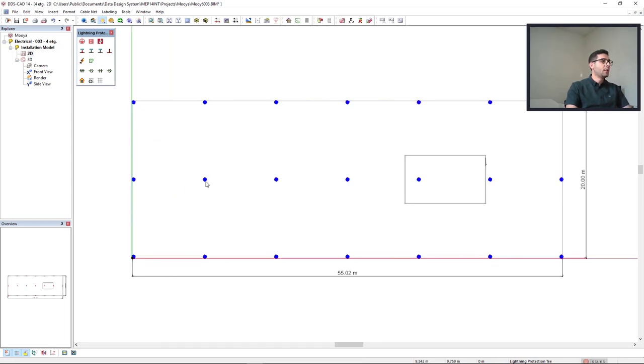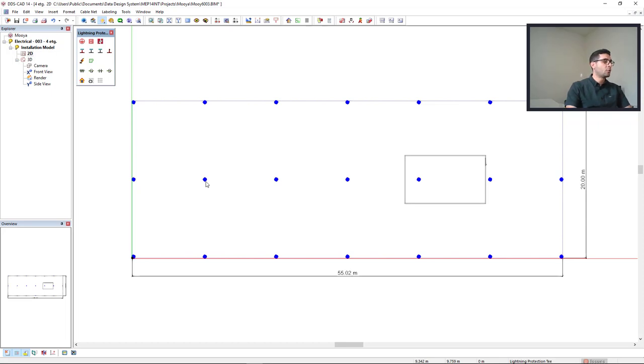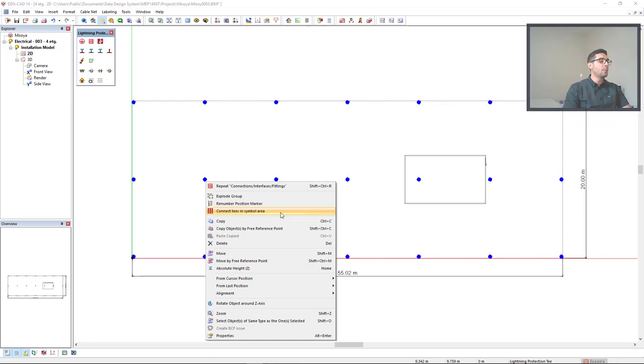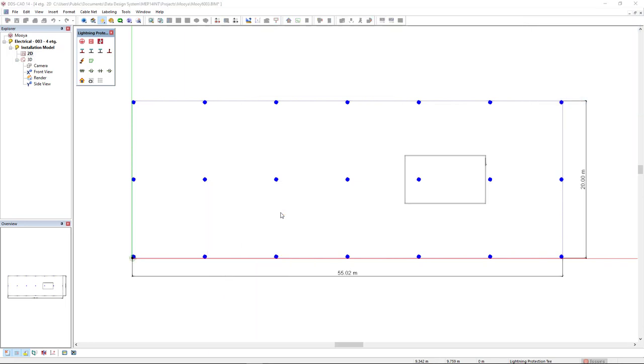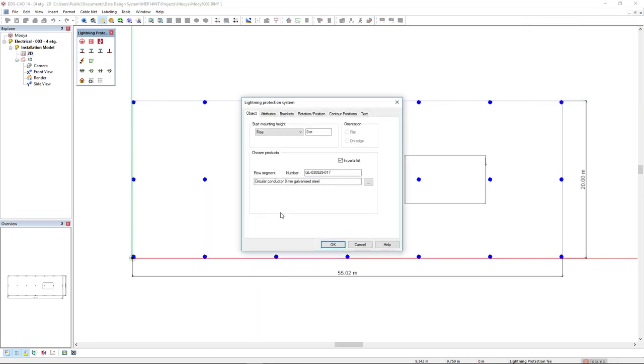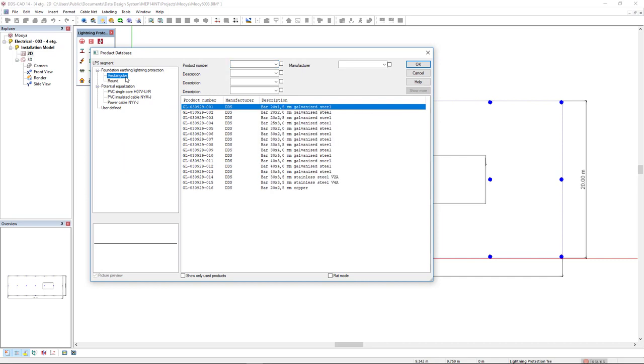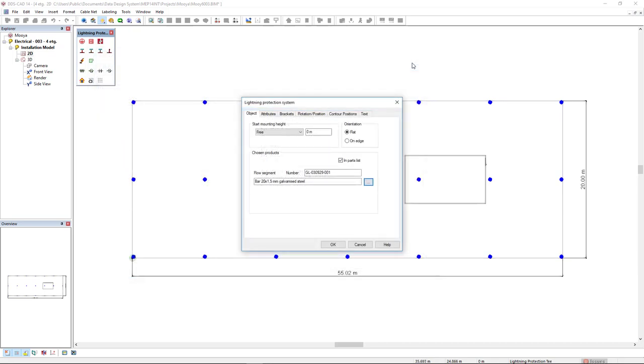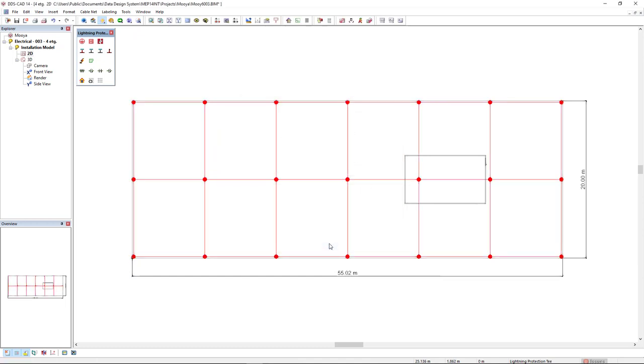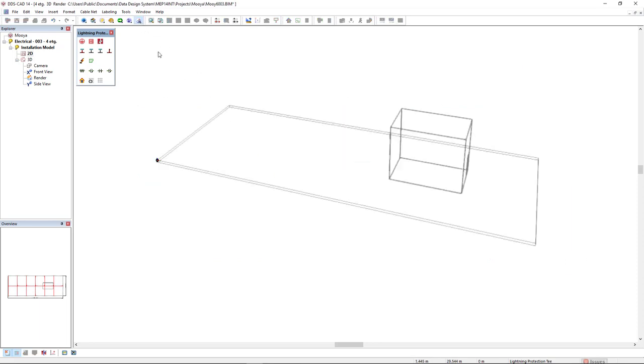Now I will left click to select this group, right mouse click and I will select this option connect lines in symbol area to create the grid cage. Now I will select the type of conductor. I will open the product database and I will select a rectangular conductor, this bar. Click ok and I will select the orientation flat and the grid is created. Now let's see the result in 3D.